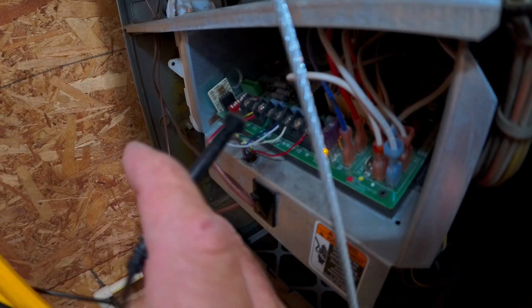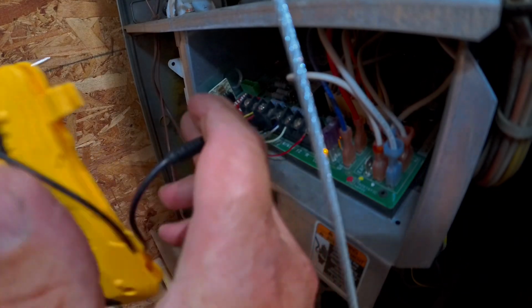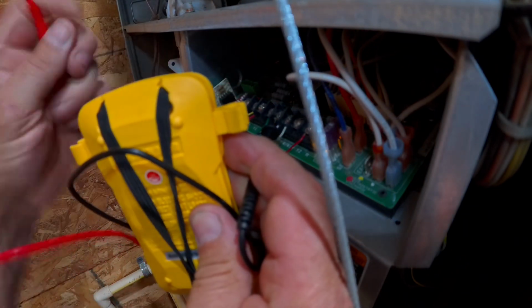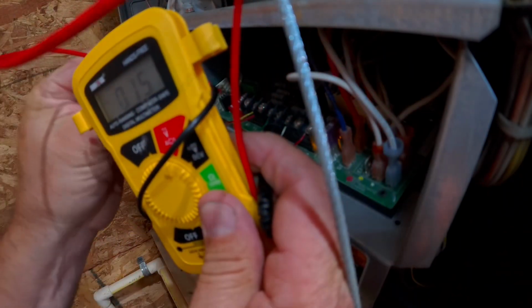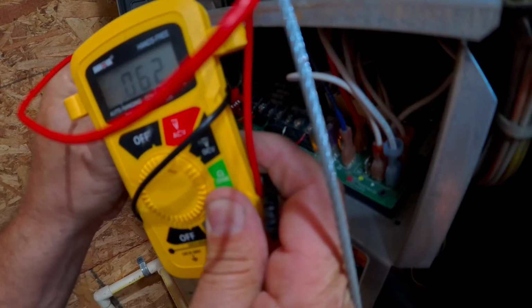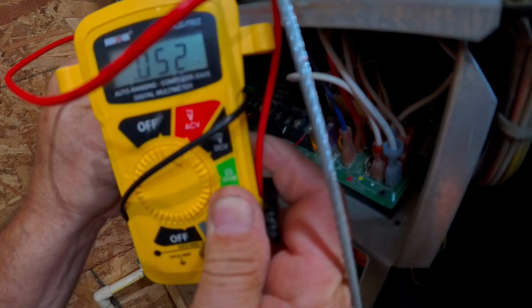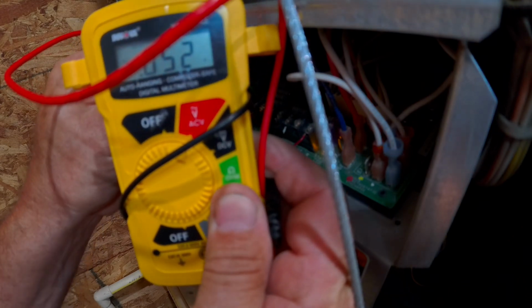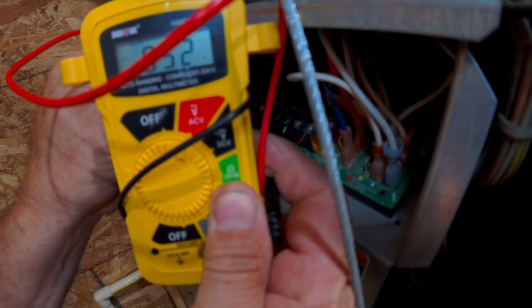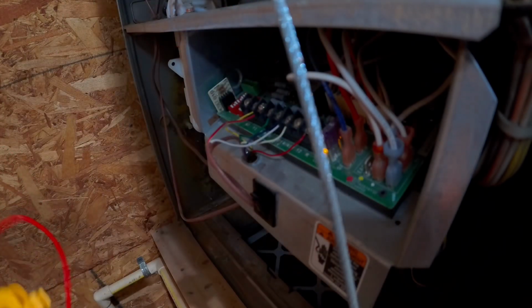So we're going to check from common with our black lead again, and then we're going to check to Y1. Well, let me turn this thing around so you can see it. Y1, what do we got? No voltage, 0.052. That is not 24 volts. That's 0.052. So again, there's no voltage there.